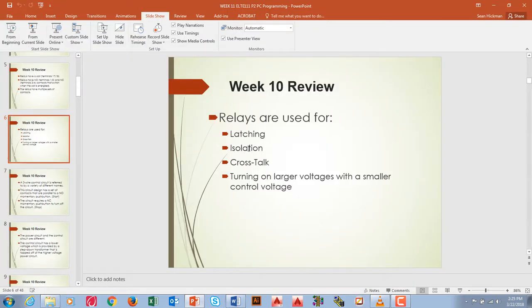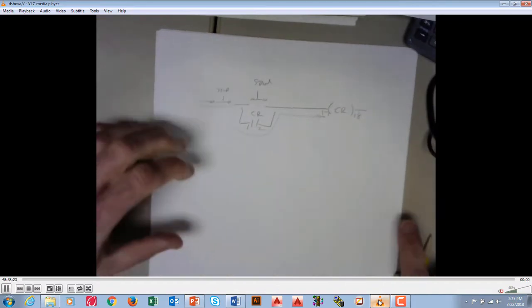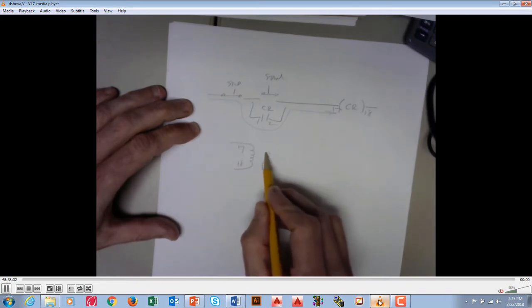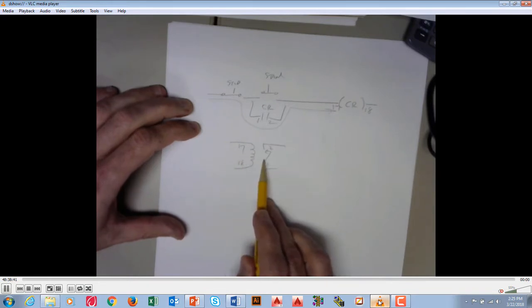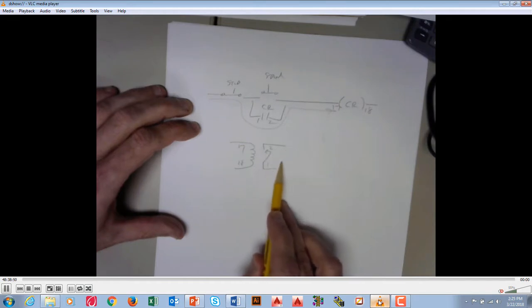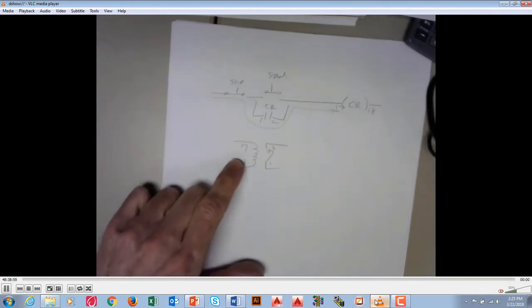The relay is used for isolation. If you had a circuit with the coil at pins 17 and 18, and then your switch at contacts 1 and 2, these aren't actually wired to each other — they work together through magnetism. When you give voltage on one side, it creates a magnet, that magnet pulls the little metal switch over and closes it, completing a circuit on the other side. They're isolated from each other — the left and right are not wired up. If you get a big spike on one side, it doesn't burn anything out on the other side.